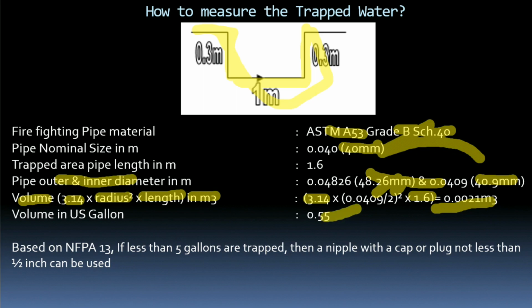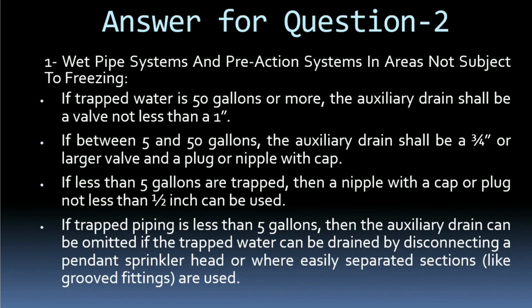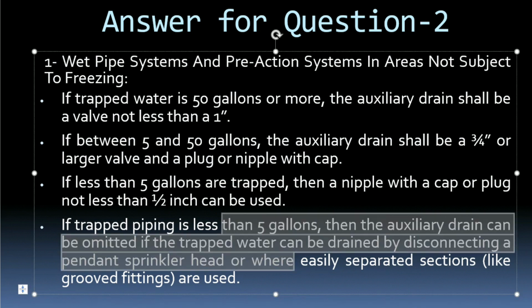As you see here, if the trapped water is less than 5 gallons, then we use the half-inch valve. Otherwise we can go with the second option: we can omit the auxiliary drain because the amount is very low. We can drain it by disconnecting a pendant sprinkler head. So this is the way to measure the trapped water.